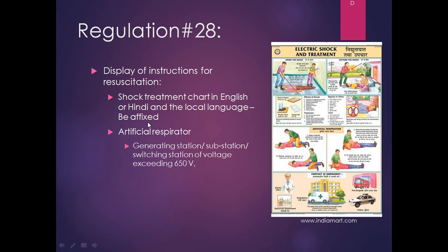What this regulation says is that a shock treatment chart in English or Hindi and the local language shall be affixed at conspicuous spaces. Suppose you have some switch gears, transformers, generators, or control gears, you affix an electric shock treatment chart there, so that if any person gets electrocuted while working, immediate first aid can be given to him just by seeing the charts, by anybody, by a layman also.